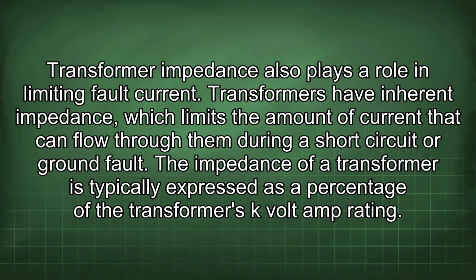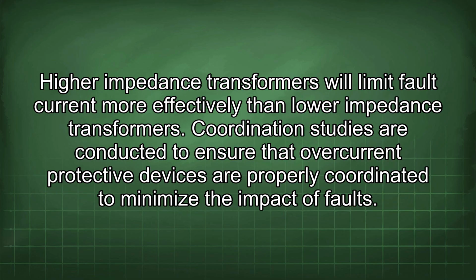Transformers have inherent impedance which limits the amount of current that can flow through them during a short circuit or ground fault. The impedance of a transformer is typically expressed as a percentage of the transformer's kVA rating. Higher impedance transformers will limit fault current more effectively than lower impedance transformers.